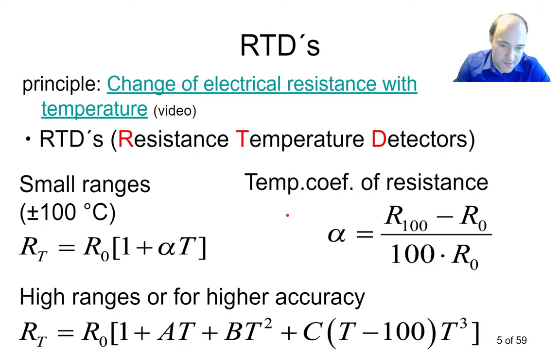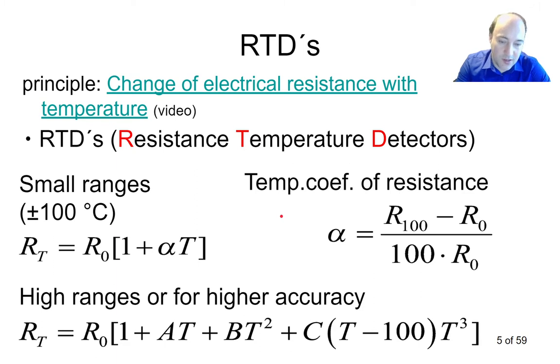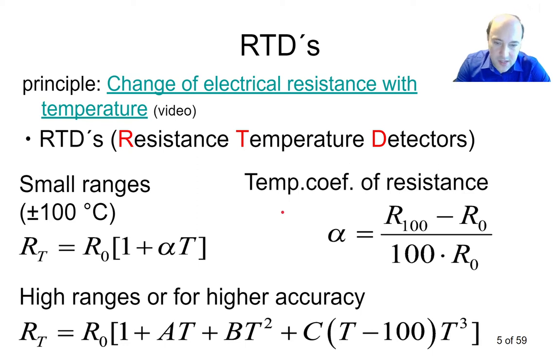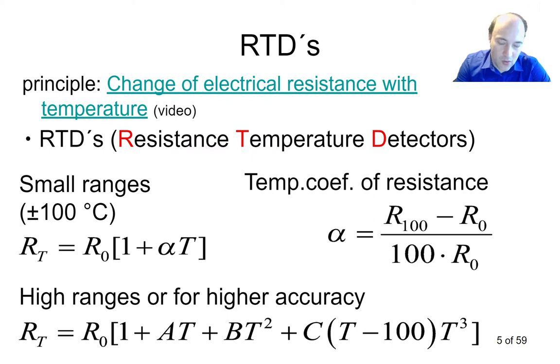Let's start. As I was saying, today we'll be repeating material from the basic class so that we all start at approximately the same level of knowledge. The first sensor I'd like to talk about is called an RTD — a resistance temperature detector. It is a sensor that changes electrical resistance with temperature. There are several types of RTDs used in industrial applications, but I will cover only the platinum sensor, because it is the most common and most accurate one, used almost exclusively in industrial applications.